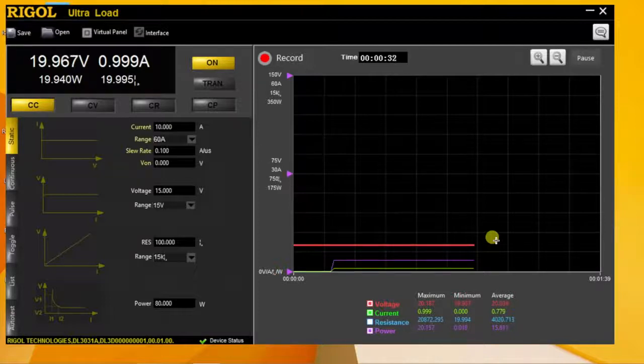Remember, you also have different ways to stop that test. We can stop it here remotely. In this case, we've programmed it automatically to stop at a certain voltage level, but it can also be programmed for capacity or time.